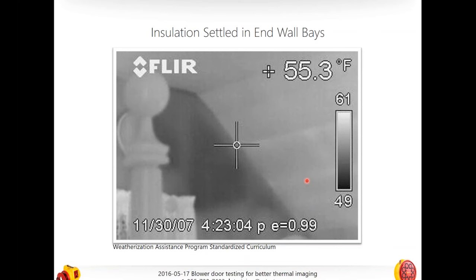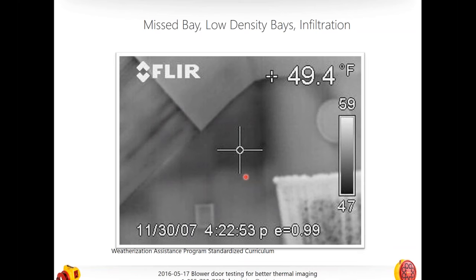Here's another example from the Weatherization Assistance Program — available free at waptac.org. This shows what happens when insulation settles in end walls in the bays of half-story buildings with side attics or Cape Cods. You can see darker portions of the wall where insulation has settled or is not applied. And here's another example of a slope ceiling with gable walls — exterior walls — with a darker spot showing an end wall with a window. The drywall has been installed over original plaster and lath, and you can see air coming down behind it.